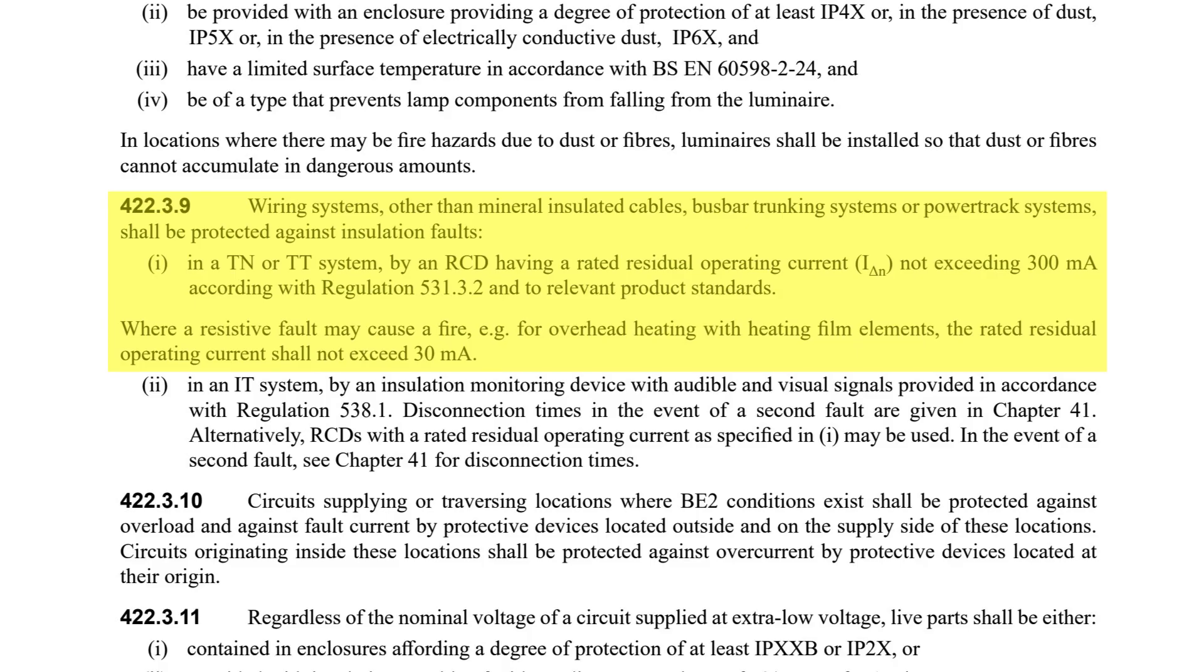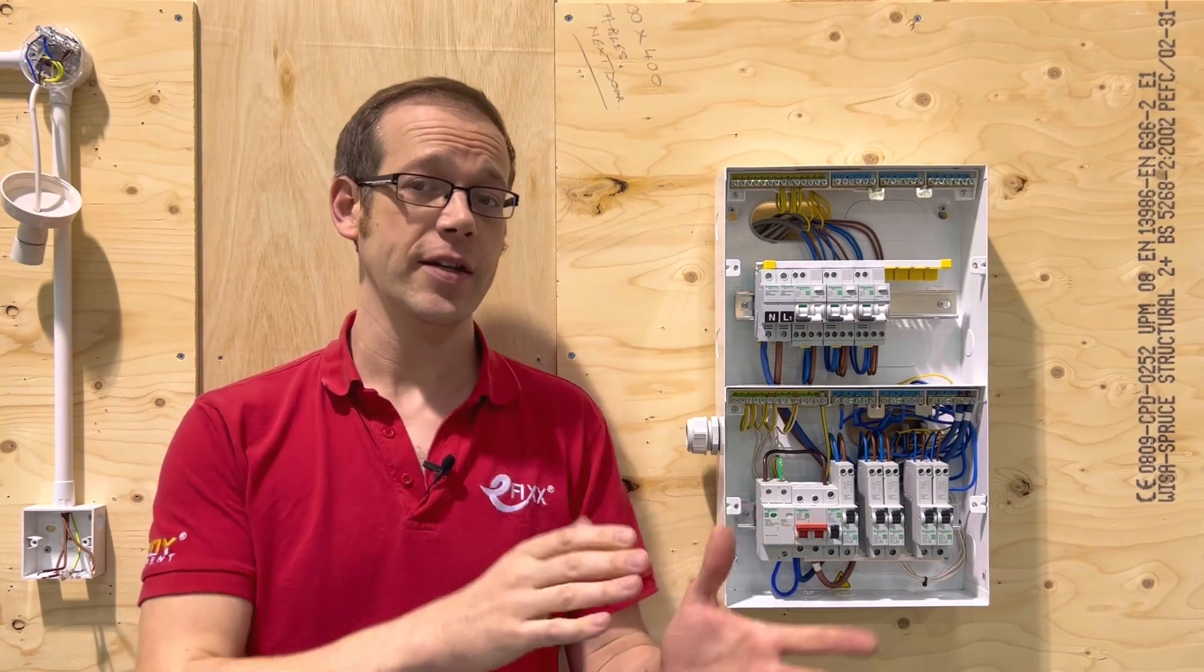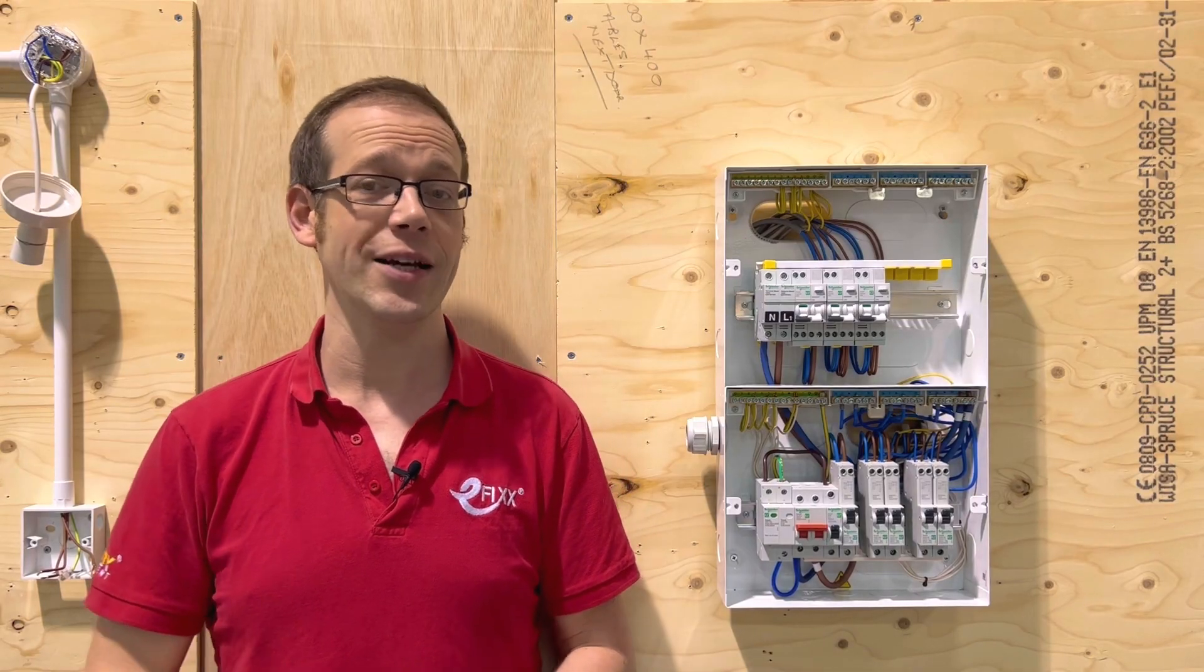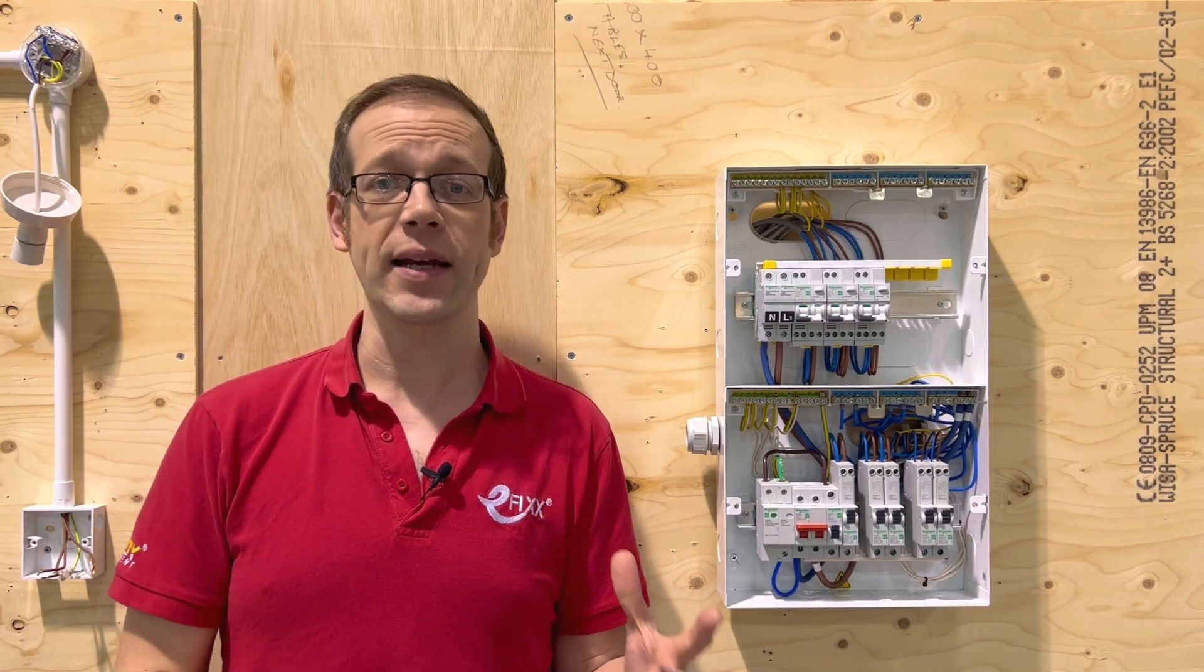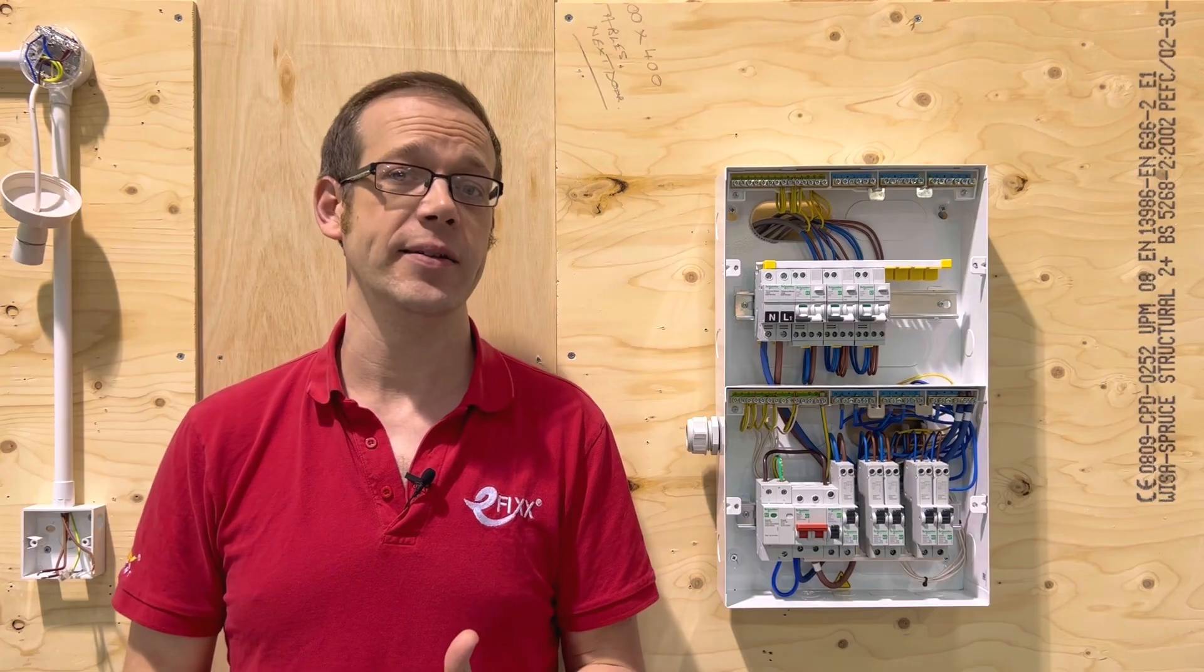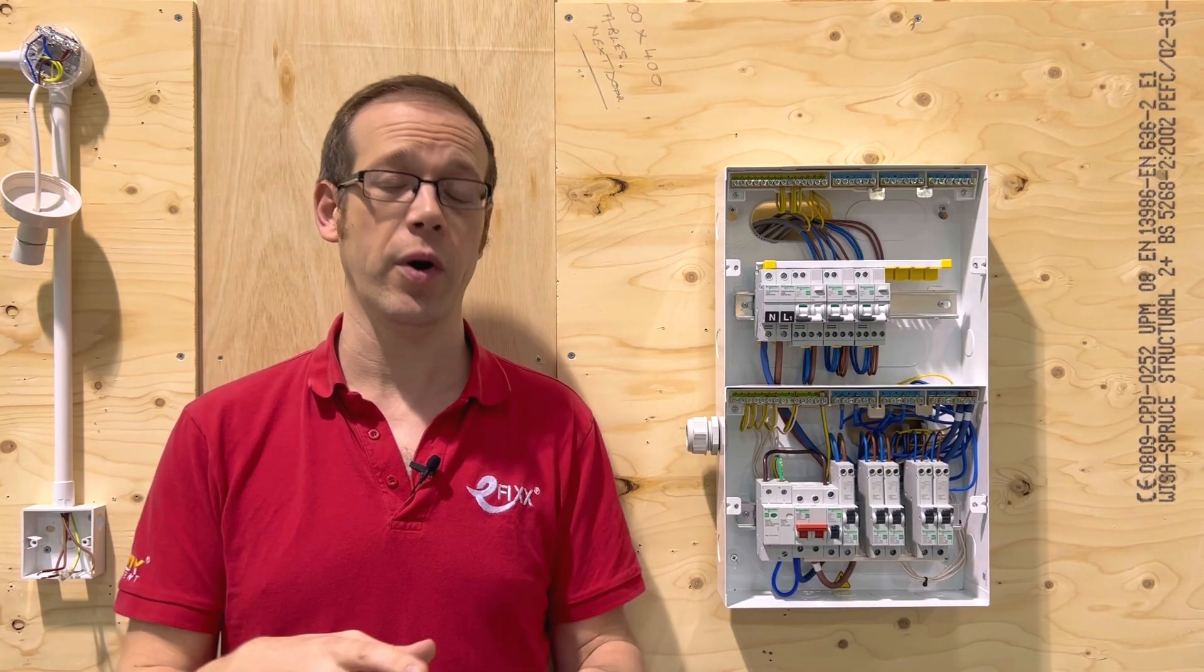Where a resistive fault may cause a fire, e.g. for overhead heating with heating film elements the rated residual operating current shall not exceed 30 milliamps. So it may be again that one of these circuits has a 30 milliamp RCD offering additional protection already but if not then you may need to provide a 300 milliamp RCD to offer protection against faults in the wiring insulation or 30 milliamps in the example given of a heating system that's using film elements overhead.